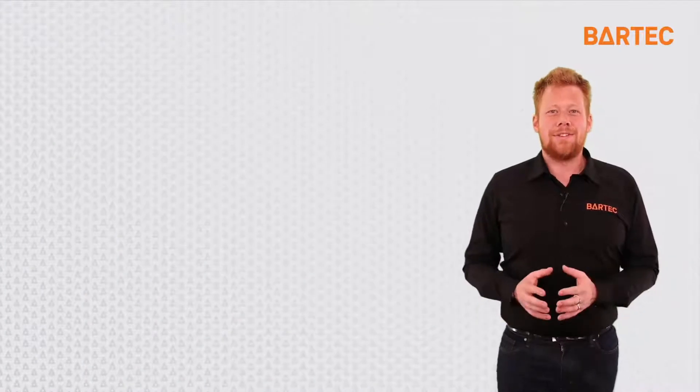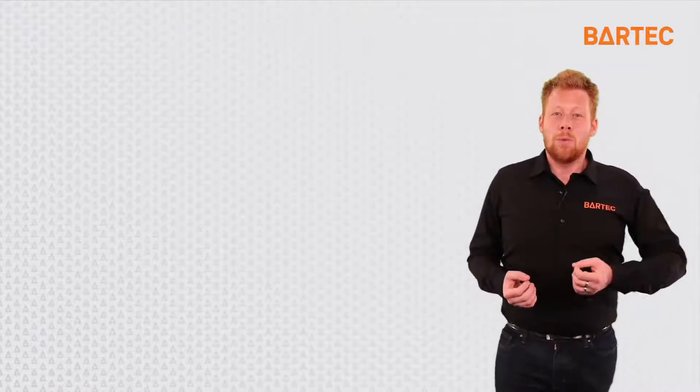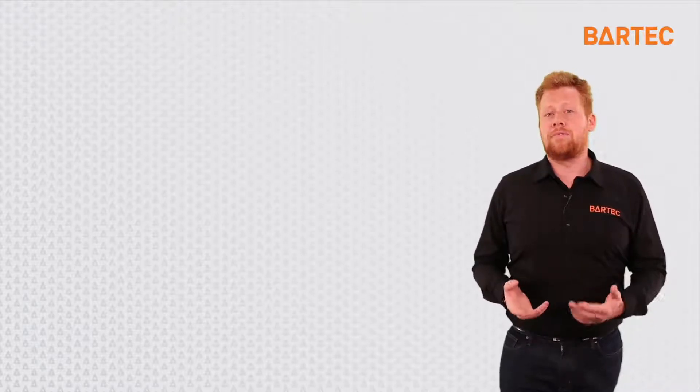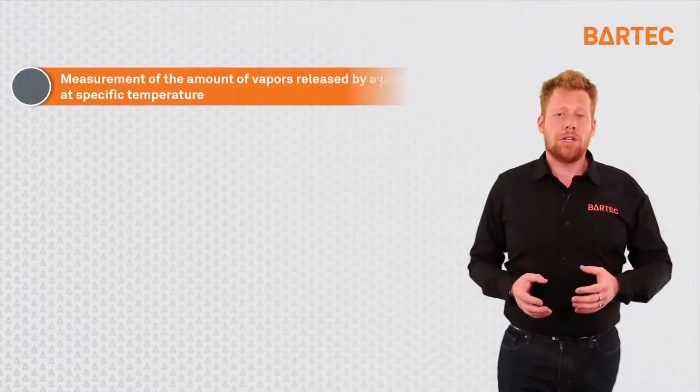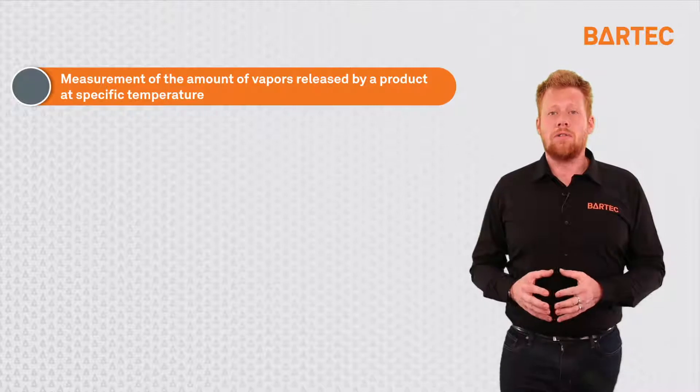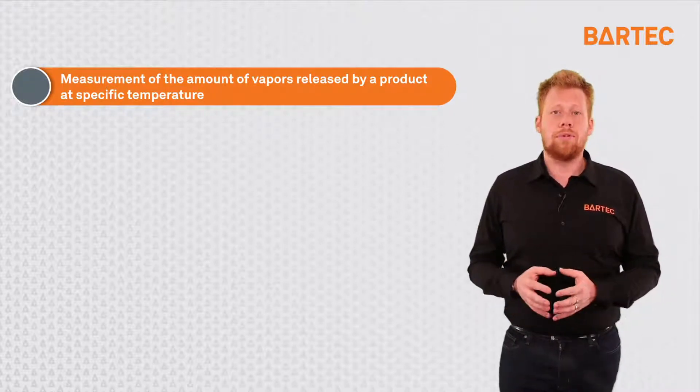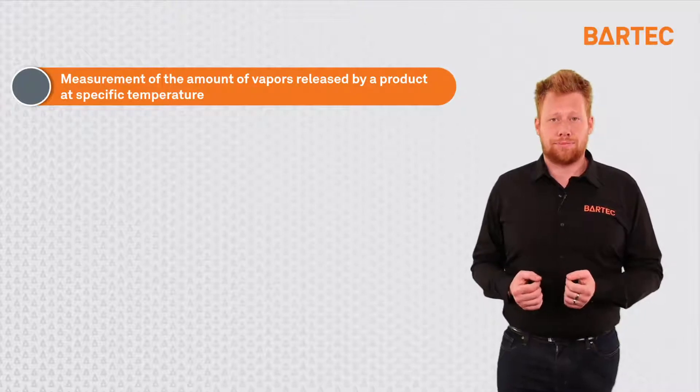Before digging further into the P700, one of the things we are often asked to do is clarify what vapor pressure is. Vapor pressure is the measurement of the amount of vapors released by a product or sample at a given temperature. How is this done in real life?